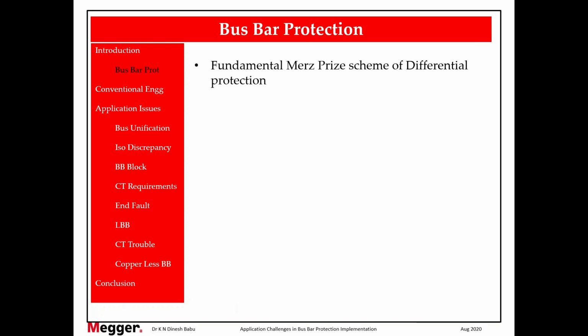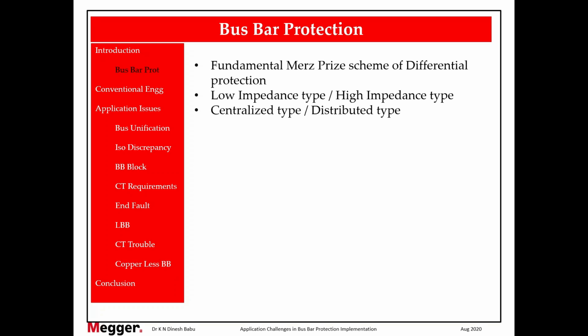So let me start with the bus bar protection. Whatever we discussed doesn't differ. It is still the same fundamental Merz price scheme of differential protection. Low impedance and high impedance, very well known. So depending on the system, whether it is single bus, we go for high impedance, or if it is complicated with a lot of isolator changeover, we go for low impedance to adapt to the dynamic bus replica.